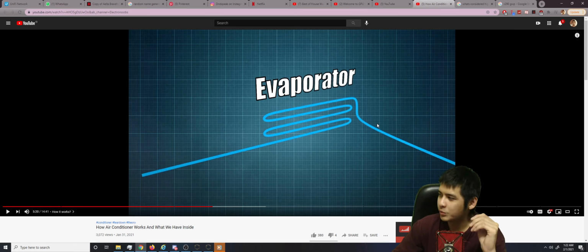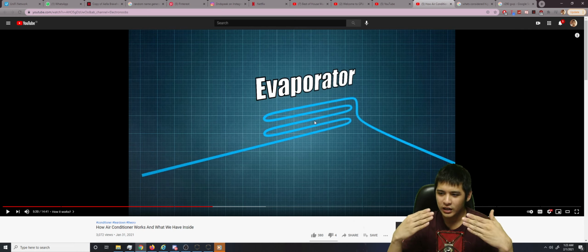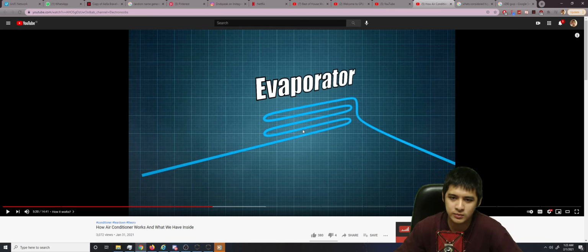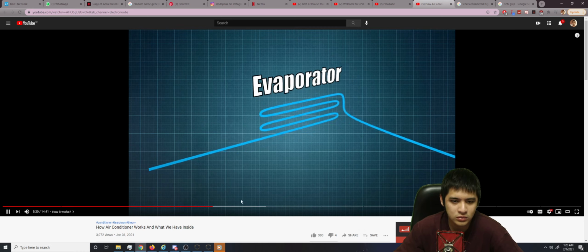Here it is. So typically, if you measure the suction temperature and the pressure, from what I heard, it's the same as if you put a probe here, in the middle. It's right in the position where you have half liquid and half gas refrigerant, and that's how you measure superheat. And that's also how you make sure all the liquid refrigerant boils off into gas, typically at the end of the evaporator, so it doesn't return to the compressor and cause damage. By the way, that's also what the suction accumulator is for. Not to remove hissing, and it's not a muffler. It's a suction accumulator.